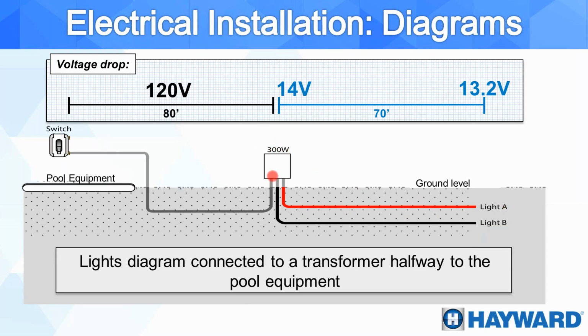Most of the transformers, at least the ones that we sell, are meant to be installed outdoors as well. So again, they can be installed at a planter or something like that. Most of the time, the closer we can get the transformer to the installation of the lights, the better, because that is going to help us avoid any kind of voltage drop.